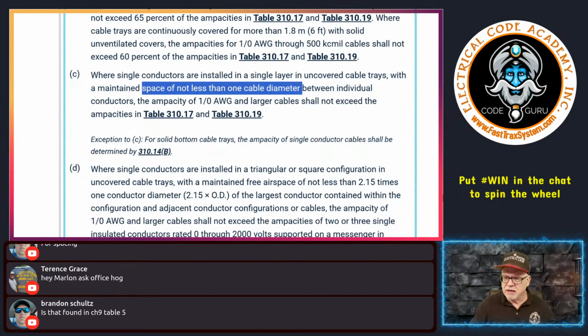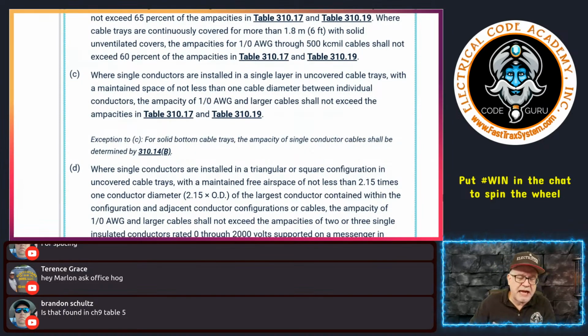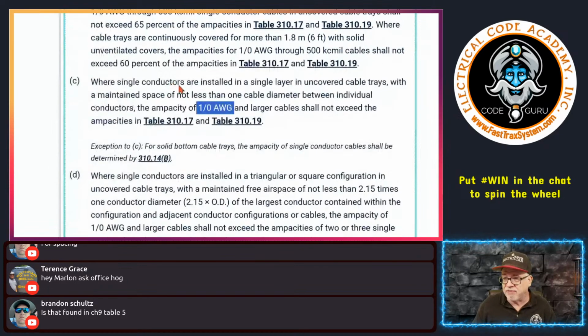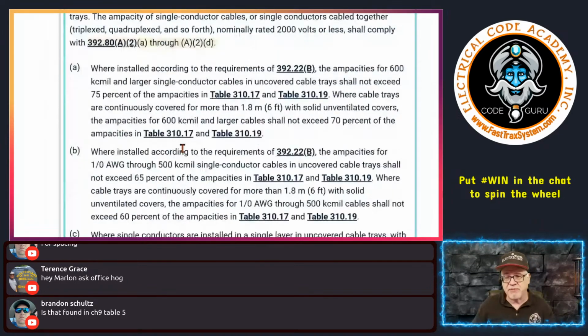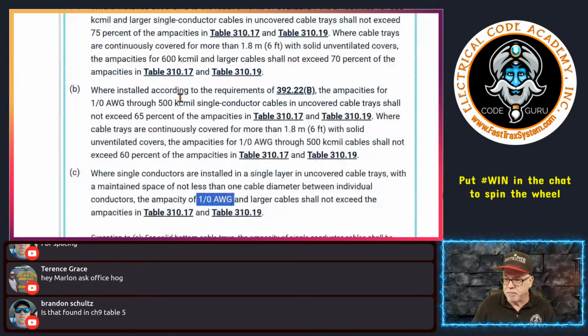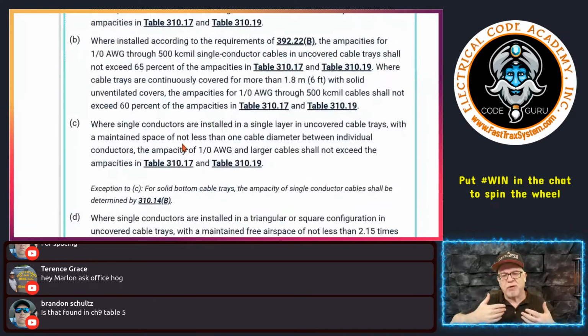So in this scenario, Chapter 9, Table 5 is only going to give you certain sizes of conductors. It's not going to give you all the sizes. It might give you 1/0, for example, for a THHN, and it might give you up to 1,000 kcmil, but it's not going to be larger than that, and you could have larger than 1,000 kcmil. Then you have to go to the manufacturers and get that information. But in real terms, with the normal stuff, like 4/0, 250 kcmil and 500 kcmil, you can get the approximate diameter of a conductor by going to Chapter 9, Table 5.